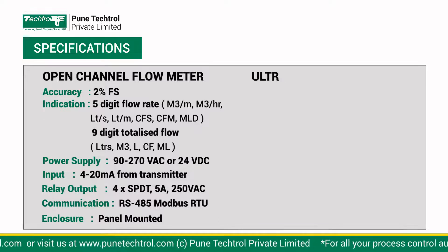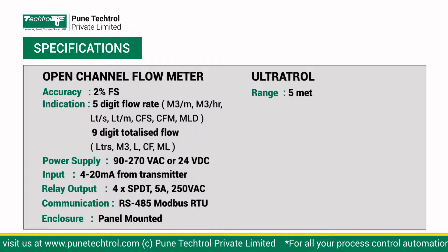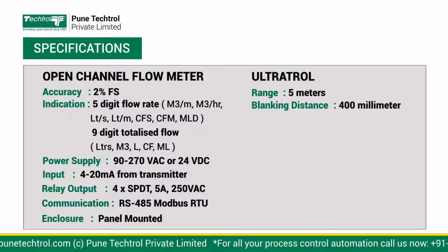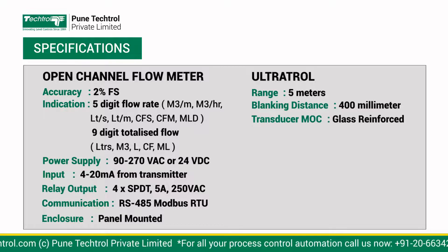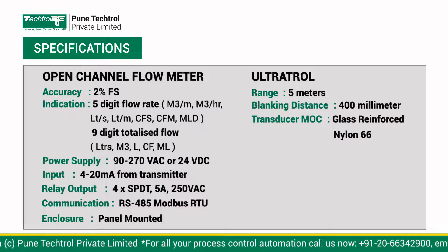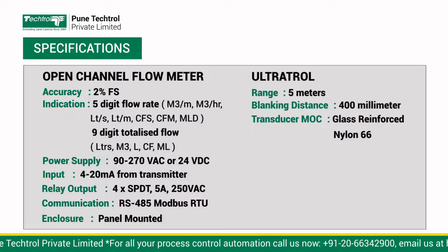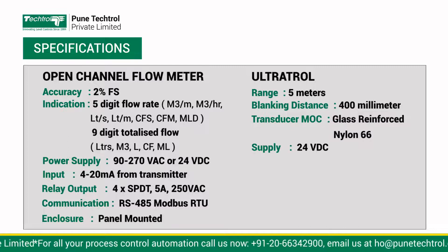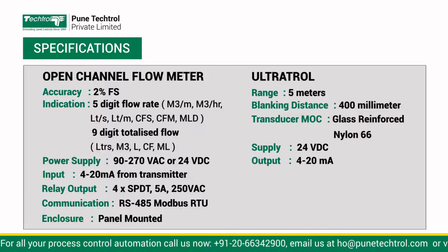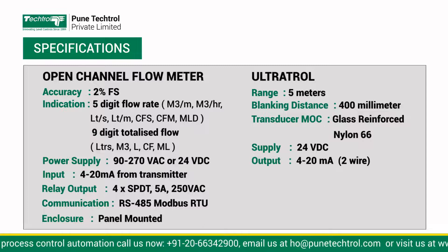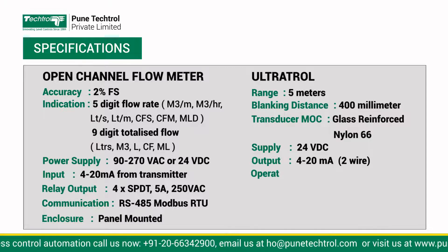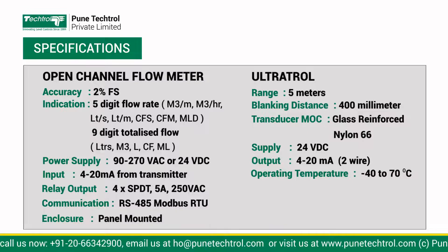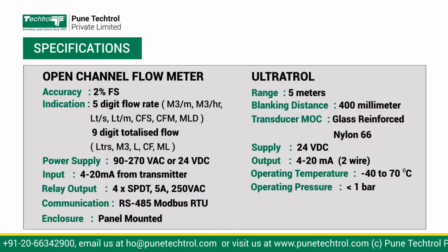Ultratrol specifications: Range 5m, blanking distance 400mm, transducer MOC glass-reinforced nylon 66, supply 24V DC, output 4-20mA two-wire, operating temperature minus 40 to 70 degrees Celsius, operating pressure less than 1 bar.